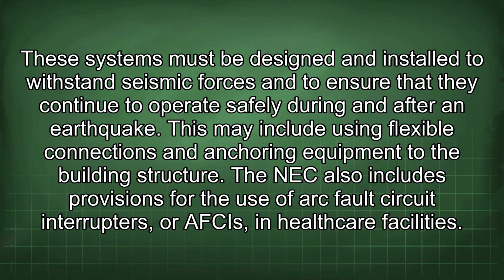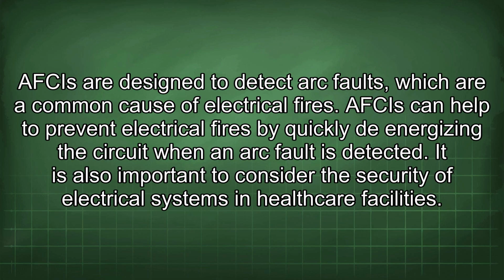The NEC also includes provisions for the use of arc fault circuit interrupters, or AFCIs, in healthcare facilities. AFCIs are designed to detect arc faults, which are a common cause of electrical fires. AFCIs can help to prevent electrical fires by quickly de-energizing the circuit when an arc fault is detected.